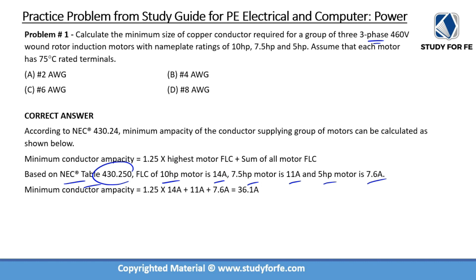Once you have verified them, it's a simple plug-and-play. So: 1.25 times 14 amps, plus 11 amps, plus 7.6 amps — which is simply the sum of the remaining motor FLCs — and that gives us a total of 36.1 amps.